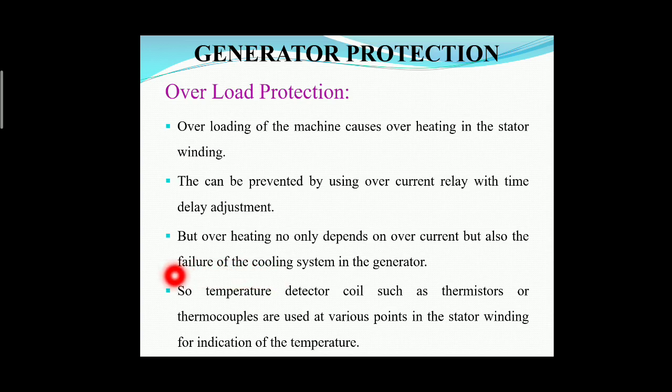Next, temperature detector coils such as thermistors or thermocouples are used. By using thermistors or thermocouples, we detect the temperatures. They are used at various points in the stator winding for indication of the temperature.